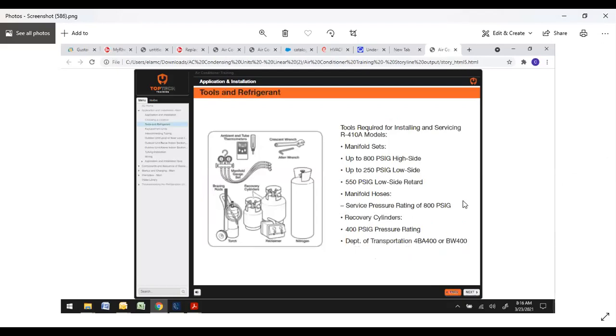Specific tools and refrigerant. All these units are 410A. Pretty much all the gauges nowadays are set up for 410A. Years ago, you had to have 2 sets. A lot of guys didn't even have 410A gauges, but you do have to have a manifold set up to 800 PSIG on the high side, 250 PSIG on the low side, a 550 PSIG low side retard. Your manifold hoses, service pressure rating of 800 PSIG.